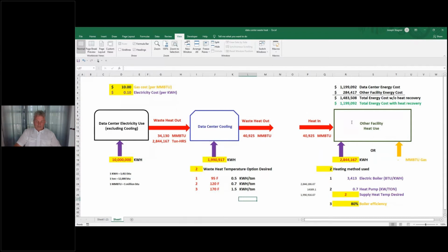If they're burning natural gas in those apartments or that commercial laundry facility, that's worth $500,000. So you say, wait a minute, I'm paying $1.2 million for electricity into my data center, getting good work out of it, but I could get another $500,000 if I put that waste heat to use every year, year in and year out, for as long as that facility runs. That cuts your electricity costs from $1.2 million down to $0.7 million. So pretty substantial savings if you harvest the waste heat with heat recovery chillers, and if you have a host that can use it.